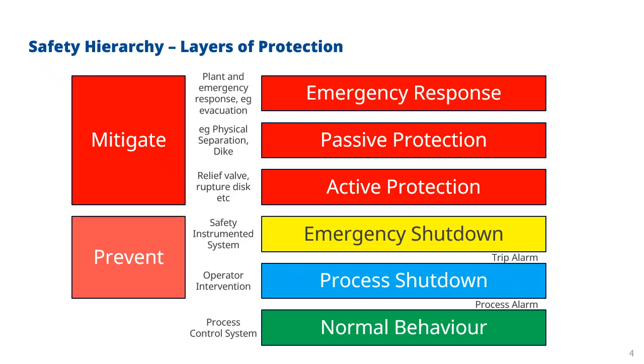Above this, then we have mitigating measures, which are when something has actually gone wrong and we're trying to prevent further serious damage or injury. So for example, there is active protection, such as relief valves and rupture discs. We can also have passive protection. That might involve physical segregation of a process plant. It might involve dikes, which can capture leaking oil, and there may be other mitigating factors there. And the final emergency response mitigating factor, that's what happens at the plant and the emergency response level, including things like evacuation and then potentially calling in third parties like the fire authorities who could maybe put out a fire or deal with whatever the event is. So there's a big hierarchy there. Where we're really concerned with what we can offer with PACSystems SafetyNet is in the yellow box there, which is the safety instrumented system.